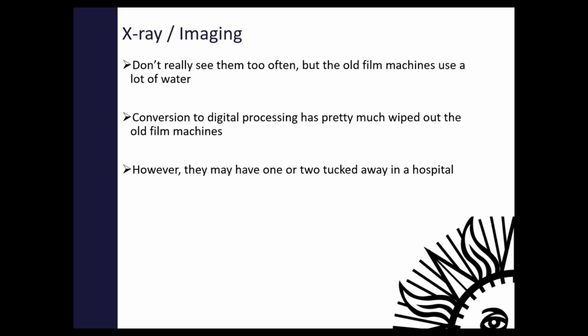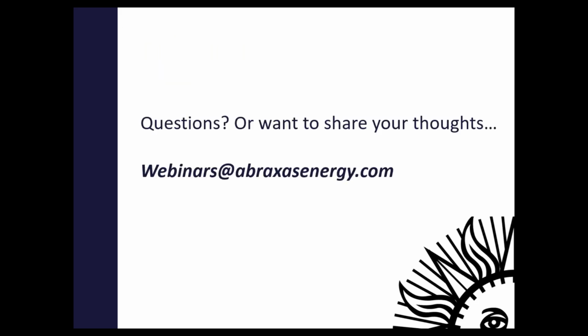X-ray machines, if there is an old machine or a film machine, they might be once through cooled with water. So that's just something to ask for in the imaging department. Make sure they have all digital equipment. Generally, if it's digital, it's cooled by a remote condenser or radiator or something like that. And that's about that. I got a question.